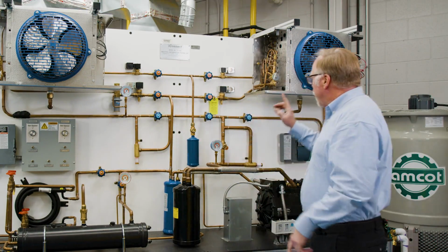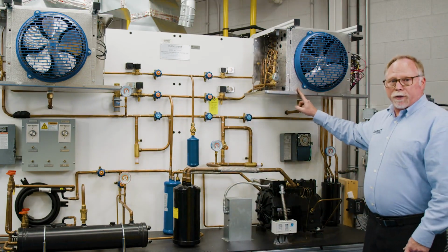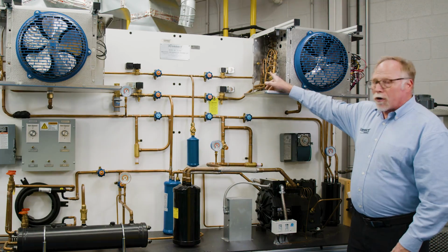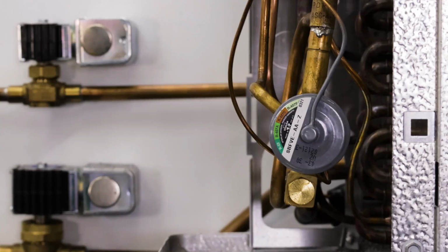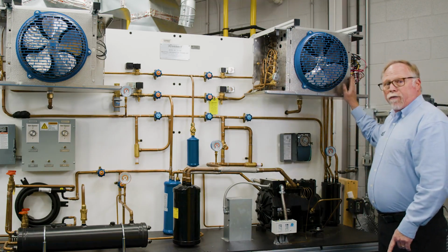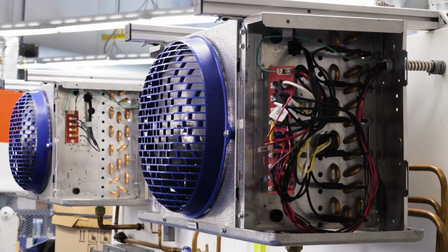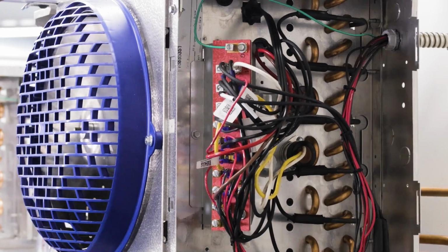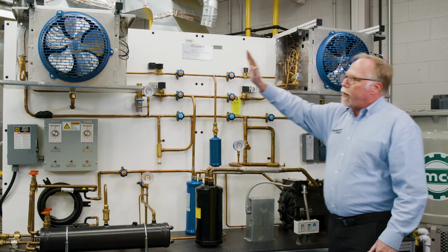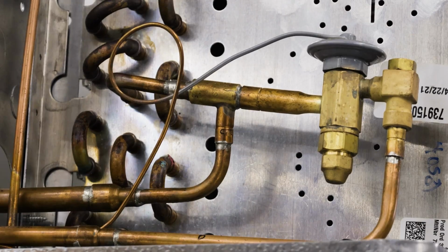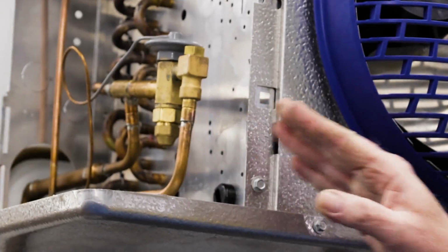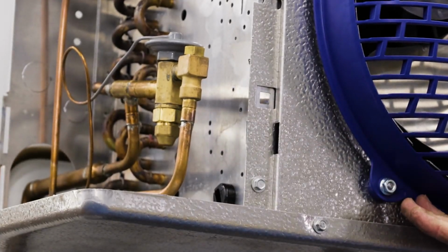On this coil here, which is our freezer, we've got an external equalizer expansion valve because we have a multi-circuited system. It also has a DFT control over here for our fans. You can bypass that if you like to get the fans going, or you can let it get cold enough to show them how it needs to bring it on with the DFT control. Over here on our medium temp coil, you can show how we've got an expansion valve, but the external equalizer is not hooked up because it is a single circuited evaporator coil.